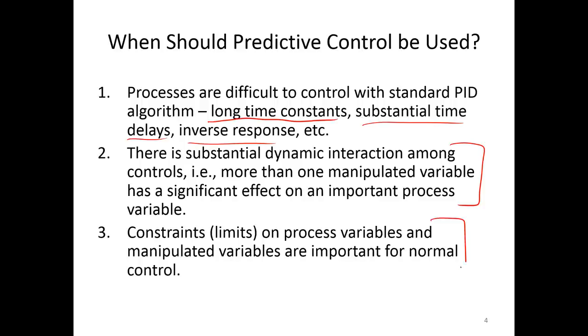Also, if you have constraints on the limits — either for manipulated variables, like a valve that can only go between zero and one hundred percent open, or a pump flow rate — or also for controlled variables, you may have upper and lower limits and want that variable to stay within those limits instead of necessarily driving to a target.